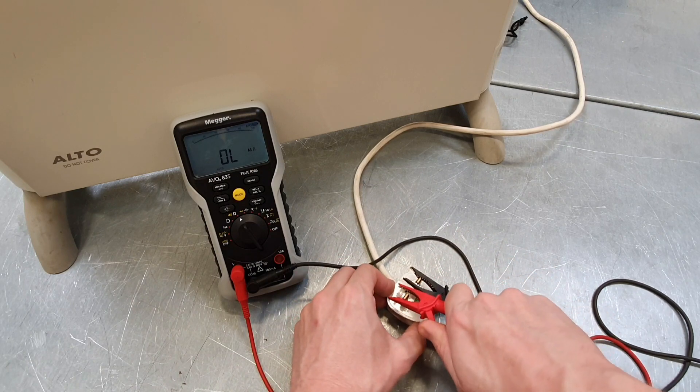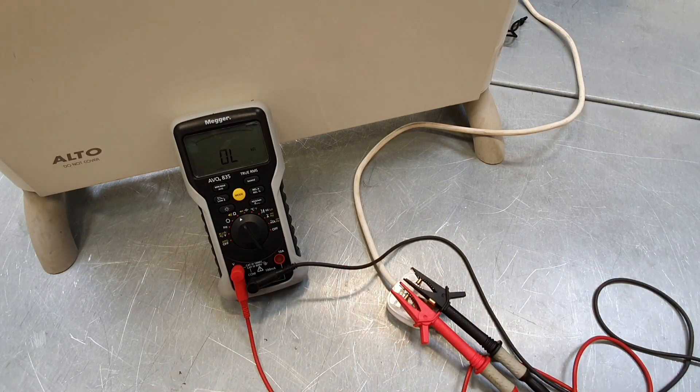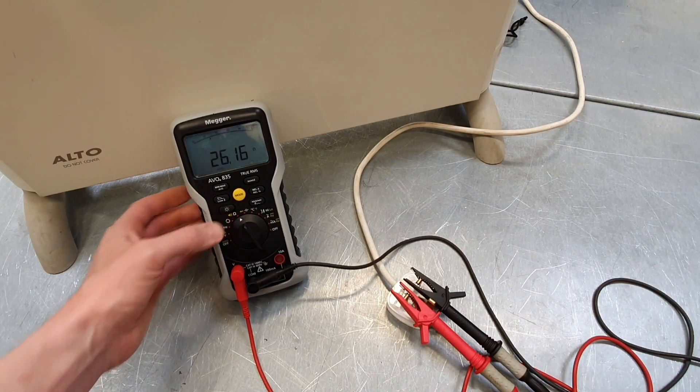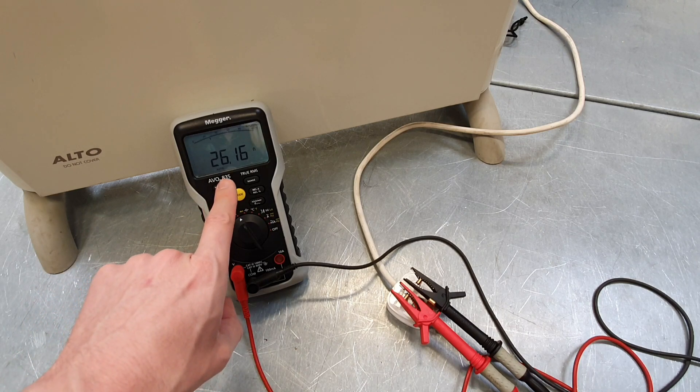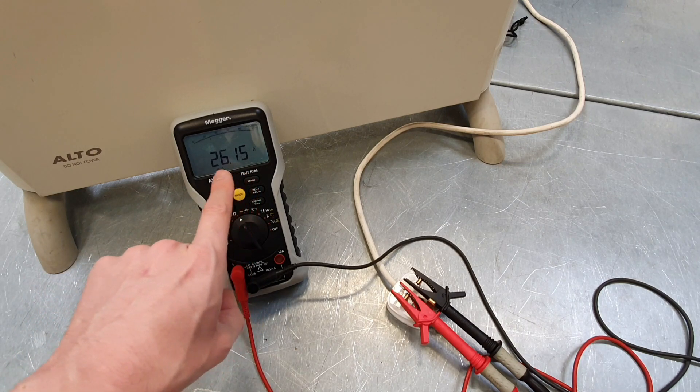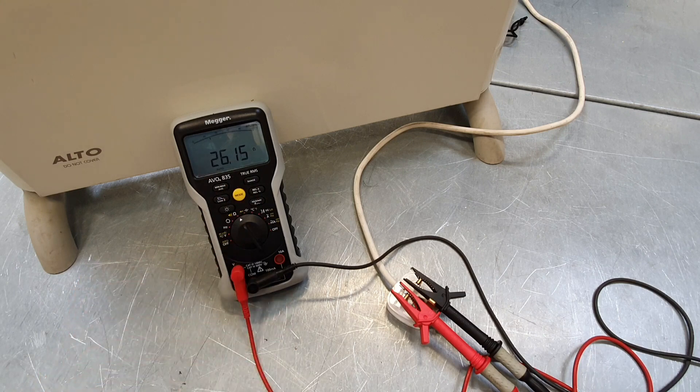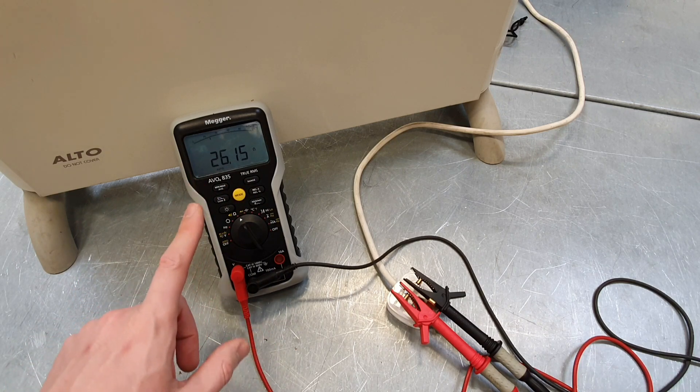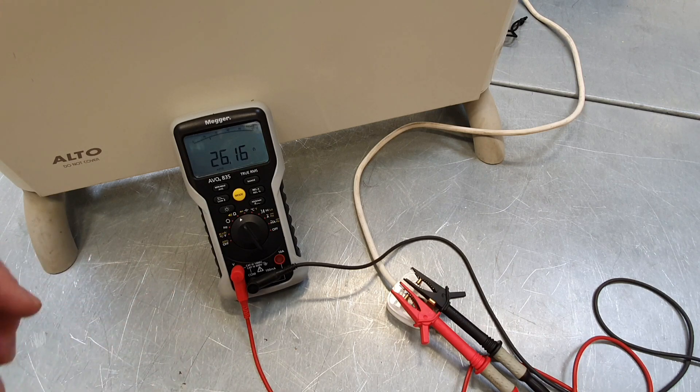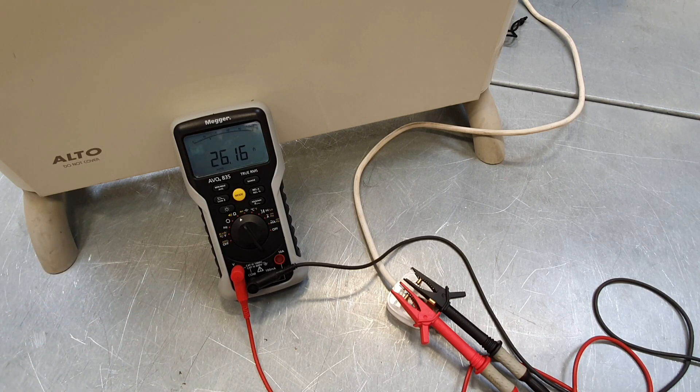So let's use our Megger AVO 835. We'll measure the resistance of the heating element here. So we'll clip that on there and we'll clip that on there. And when we measure that we see we're coming out with 26.16 ohms. So that's 26.16 ohms. It's hovering around out there. So let's take those numbers back up to the classroom and we'll have a look at whether that formula actually works or not.